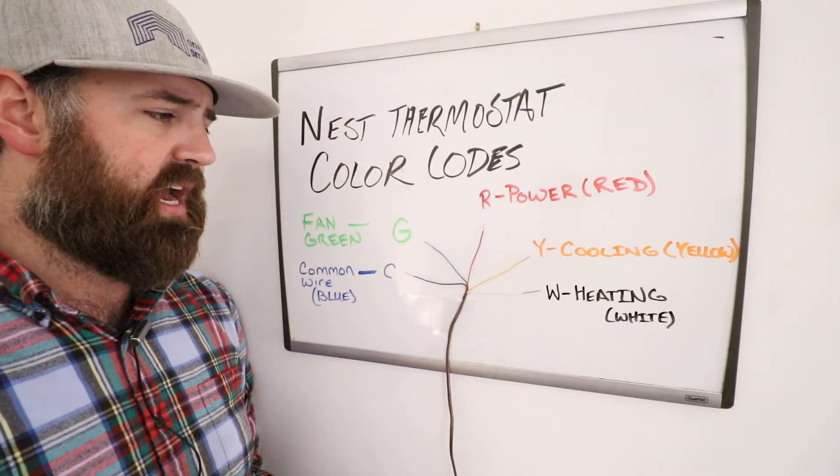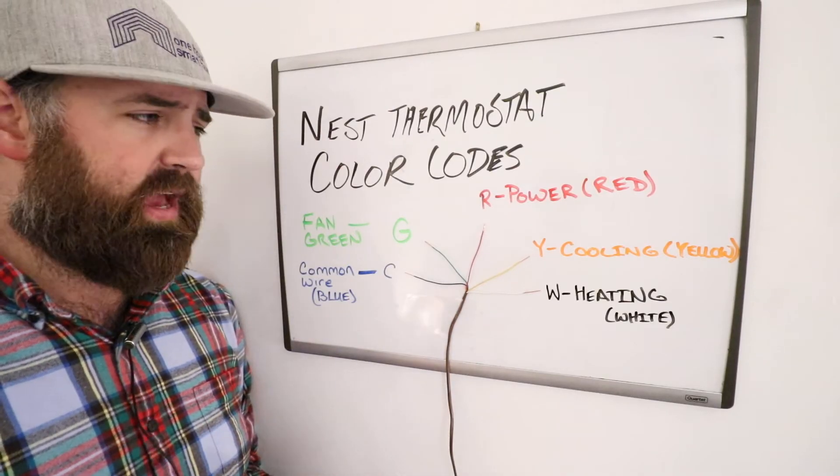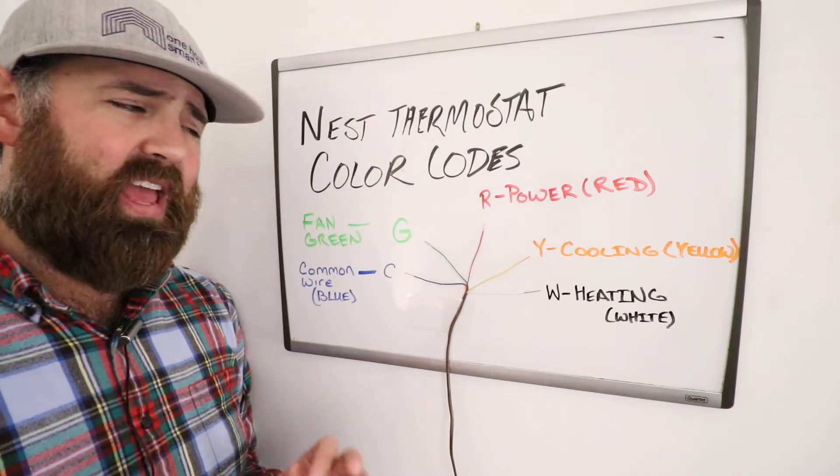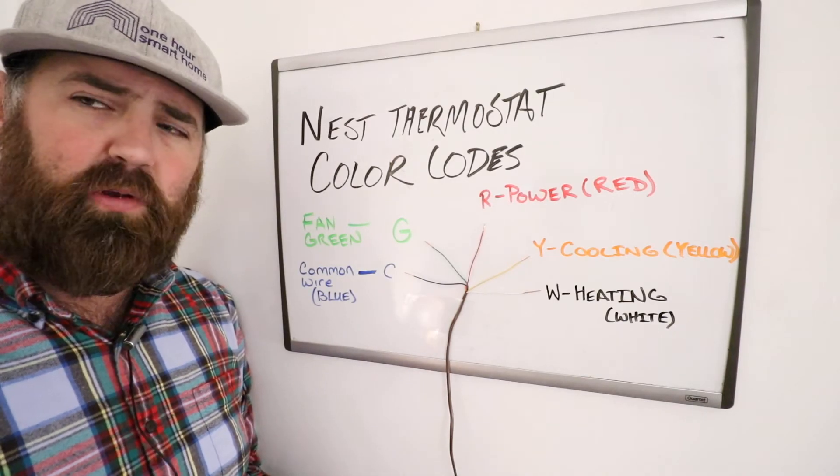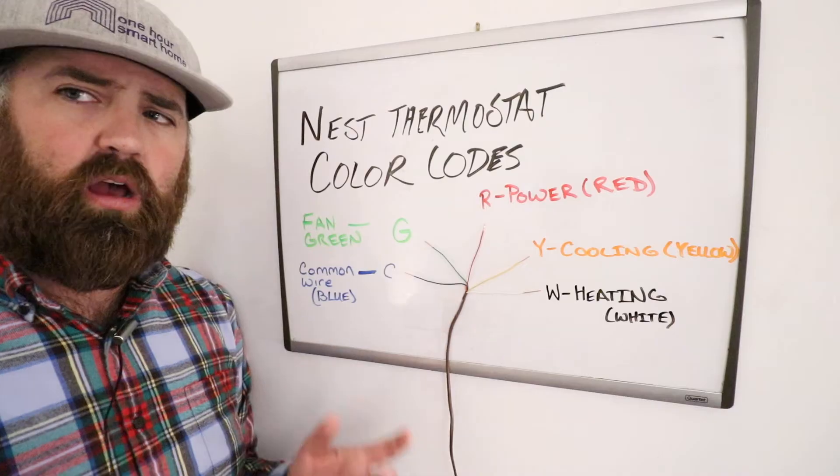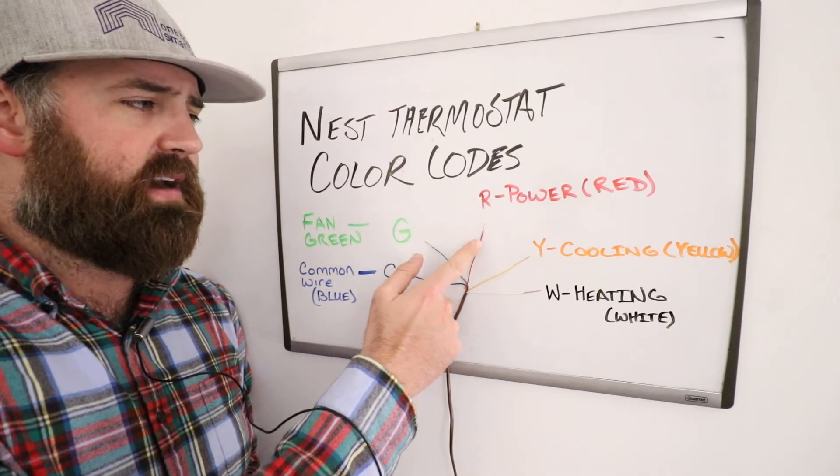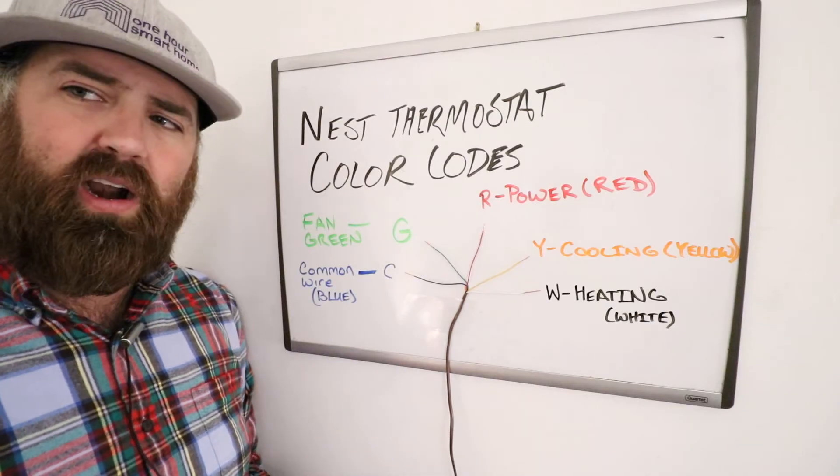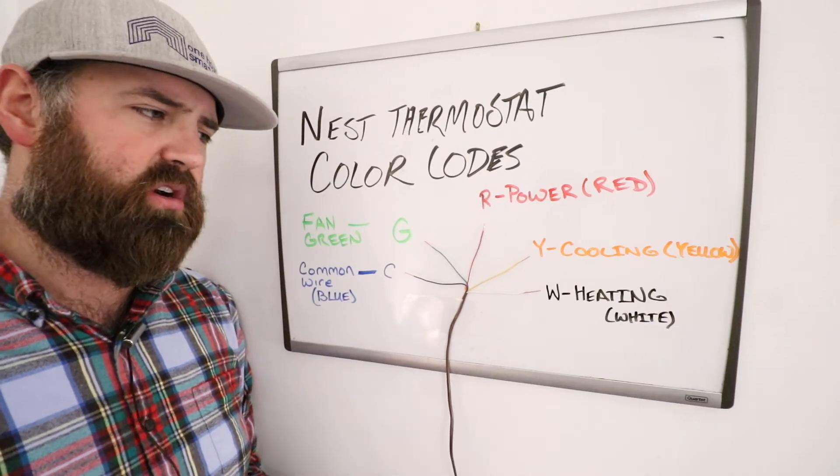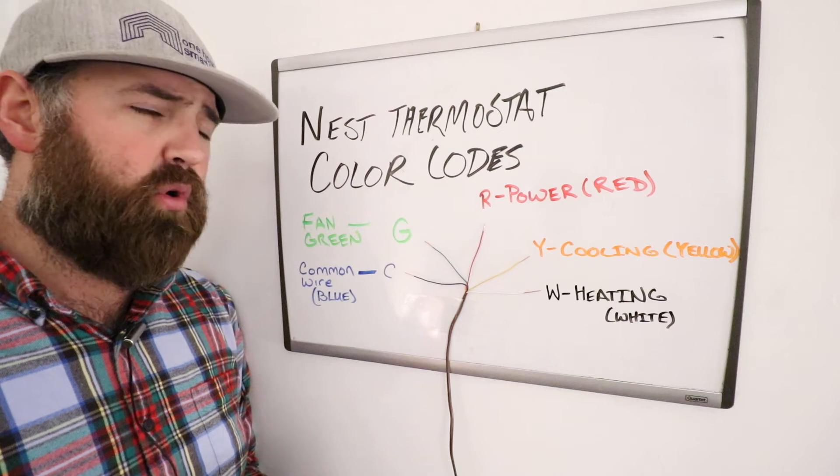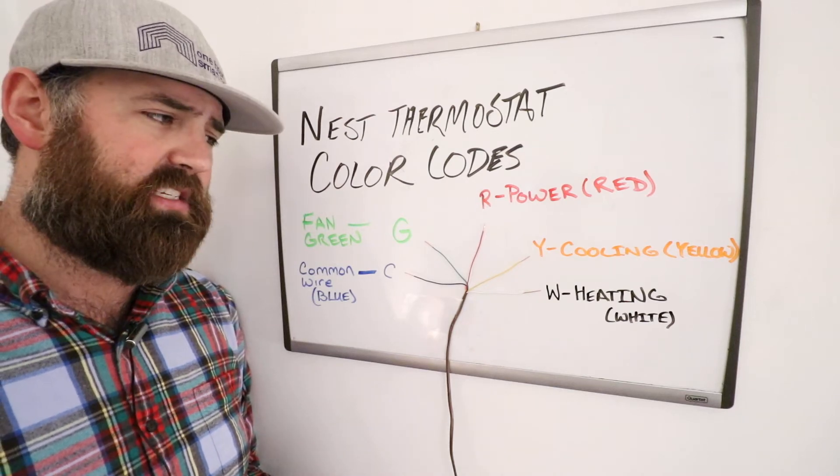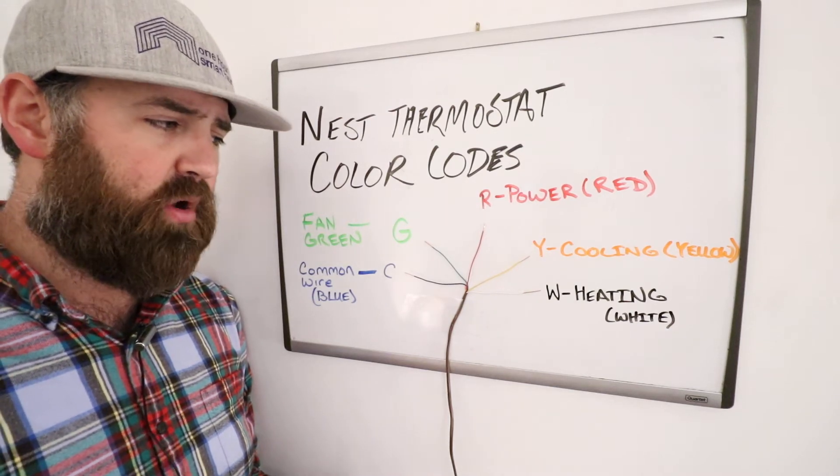Now let's say you only had two wires, which some of you do only have two wires, and typically that is a furnace-only system. Maybe you live somewhere where it doesn't get hot enough that you need air conditioning. In that case, you would really only need to have an R-wire, the power wire, and the W-wire, and that would activate your furnace and turn on your furnace. Or if you had a boiler, same thing for the Nest boiler and heating mode only.